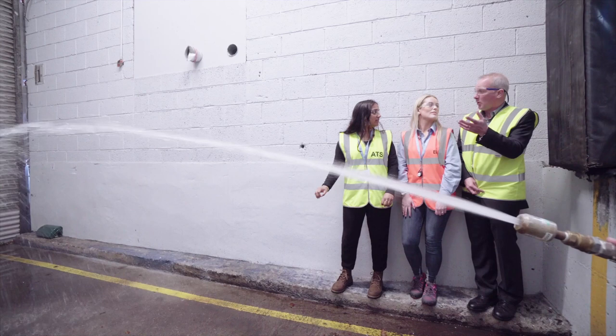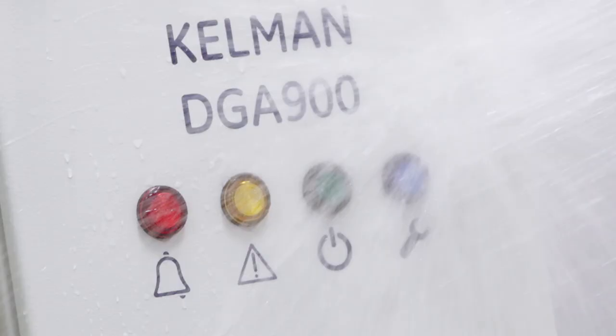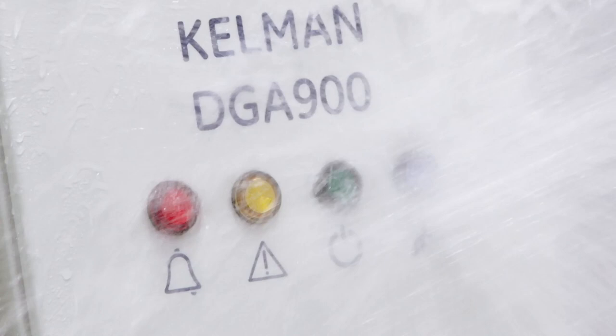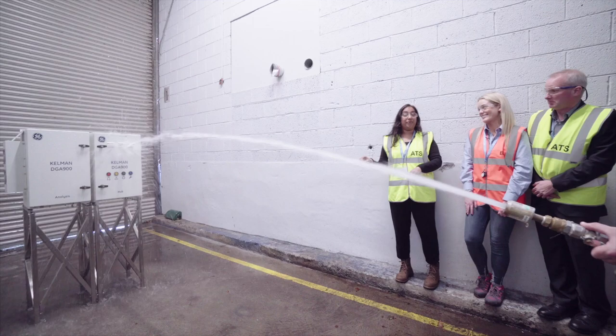So Zainab, this is a really important test for our customers. Obviously, as well as rainwater getting on their units, it's important that when our customers are power hosing their assets, the water's not getting inside of our unit. It makes sense. That's a lot. How much water is that? That's 100 litres per minute. Wow. Impressive, isn't it? That's crazy.